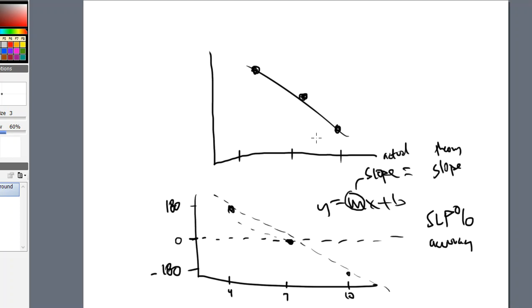So if there was only a 2-point calibration, what could happen is that, let's say that my 7 wasn't used. Let's say that my 7 wasn't run, and my 10 actually gave me a point like up here instead of where it needs to be. Well, I don't have a third point to go by. So what would happen is that this would significantly skew my numbers, because my graph would somewhat do, if I could draw a straight line.